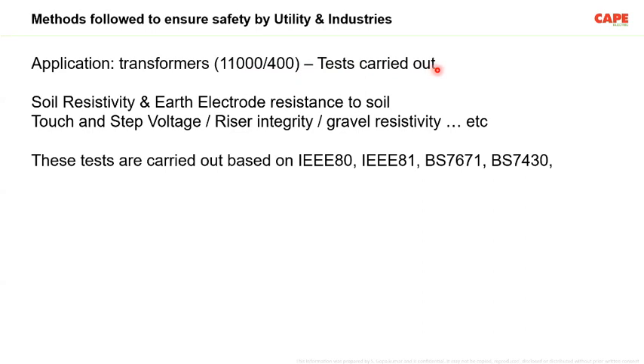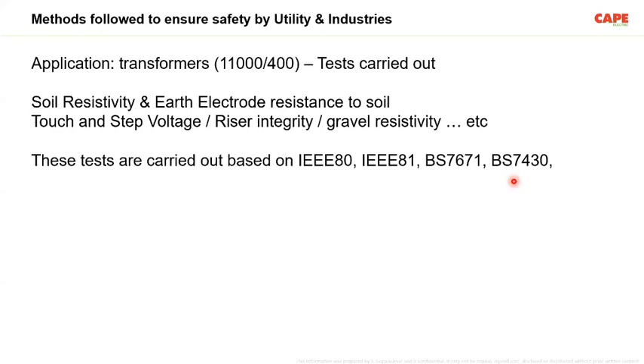The people wanted to make a test. They believe that making the soil resistivity test, earth electrode resistance test, plus touch and step voltage, riser integrity, gravel resistivity, and a long list of tests. A lot of engineers are asking me to support them to make these tests like step voltage, riser integrity, gravel resistivity, and all those things. And they wanted to do the test as per IEEE 80, IEEE 81, BS 7671, BS 7430, and all. Unfortunately, only a little bit about the Indian standards is requested.